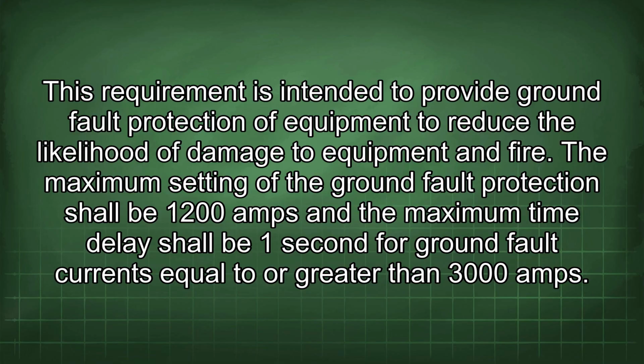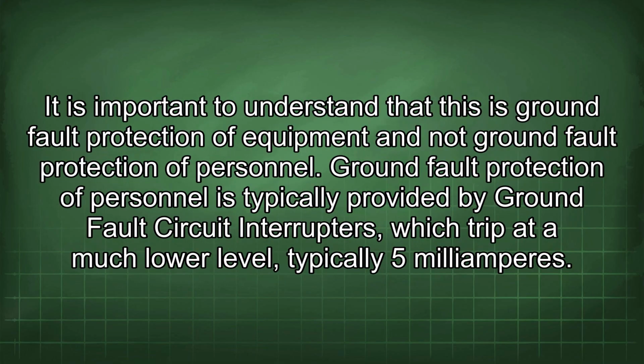This requirement is intended to provide ground fault protection of equipment to reduce the likelihood of damage to equipment and fire. The maximum setting of the ground fault protection shall be 1200 amps and the maximum time delay shall be 1 second for ground fault currents equal to or greater than 3000 amps. It is important to understand that this is ground fault protection of equipment and not ground fault protection of personnel. Ground fault protection of personnel is typically provided by ground fault circuit interrupters, which trip at a much lower level, typically 5 milliamperes.